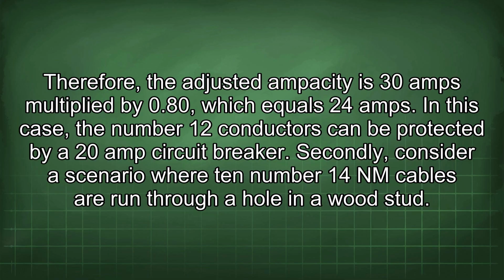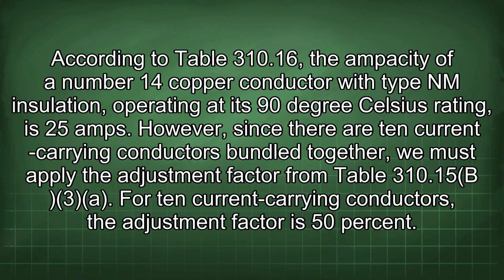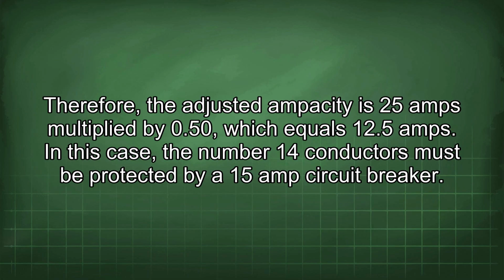Secondly, consider a scenario where 10 number 14 NM cables are run through a hole in a wood stud. According to Table 310.16, the ampacity of a number 14 copper conductor with type NM insulation operating at its 90°C rating is 25 amps. However, since there are 10 current carrying conductors bundled together, we must apply the adjustment factor from Table 310.15(b)(3). For 10 current carrying conductors, the adjustment factor is 50%. Therefore, the adjusted ampacity is 25 amps multiplied by 0.50, which equals 12.5 amps. In this case, the number 14 conductors must be protected by a 15 amp circuit breaker.